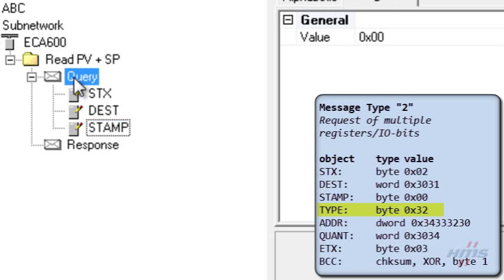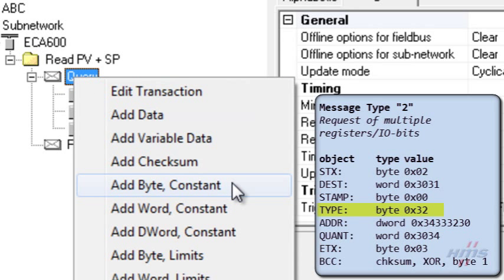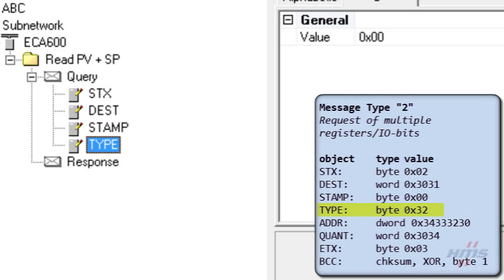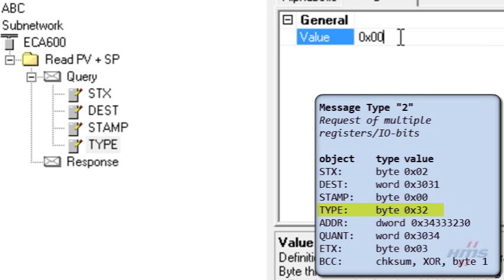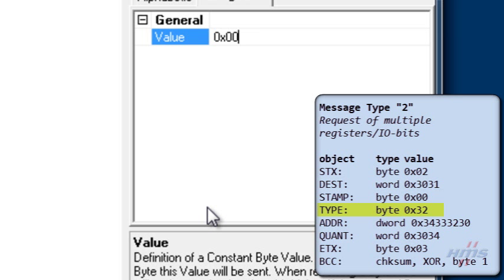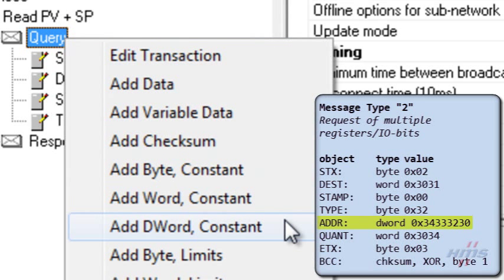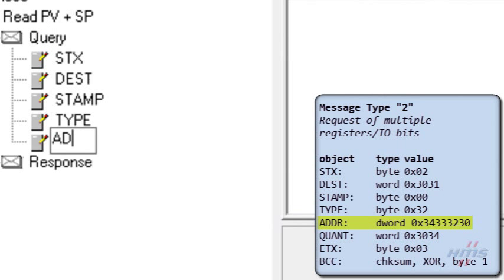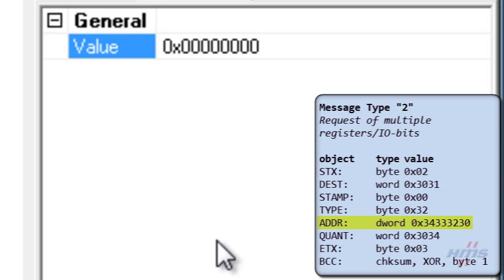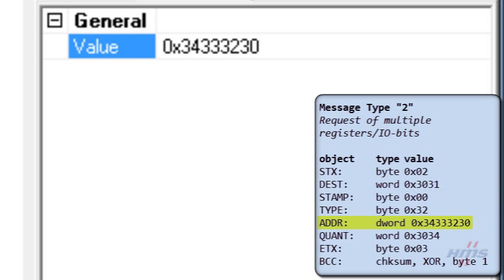A constant byte is added for the type object. The value we set to hexadecimal 32, meaning message type 2. We add a constant double word for the address object. The hexadecimal value we set to 34333230, meaning address 4320, which is the address to register 50.